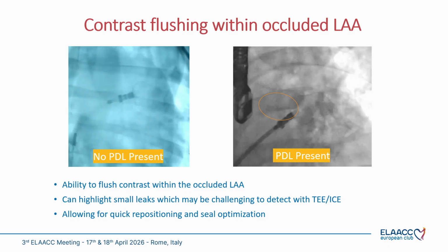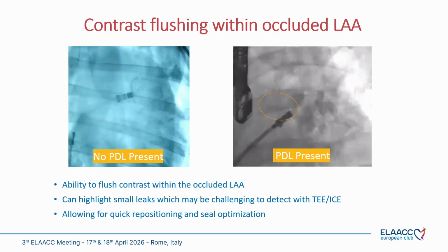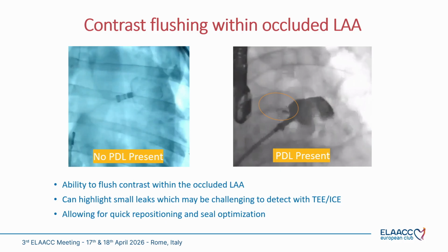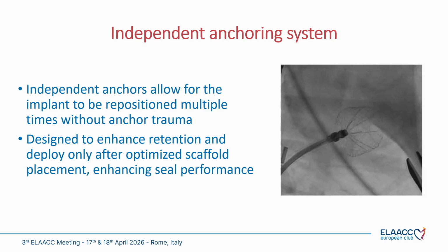So this is then the contrast flushing inside the device. You see here, for example, on the left-hand side, you inject the contrast in the device. You confirm there's no leak. And when you're happy, then you deploy the anchors and you release. On the other hand, keep an eye on the right-hand side. You give some contrast within the device and you clearly see there's still some remaining gap and some leak. So then you have the possibility to reposition your device and try to get a more optimal position. This video should also run. Yeah, here you see very clearly how these hooks, these anchors, come out.